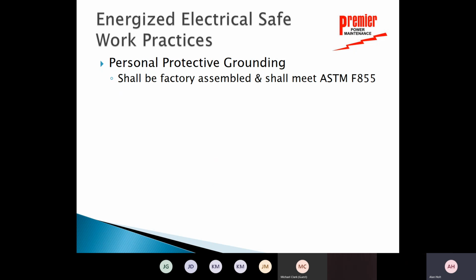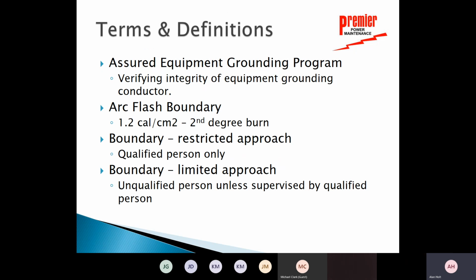Then the point I mentioned earlier about personal protective grounding, their policy is it shall be factory assembled. So our ground sets would not be acceptable because we build those ourselves. We meet all the ASTM requirements, but it's not factory assembled. Assured equipment grounding program. If we're using extension cords, they have to have been tested in the last 3 months.